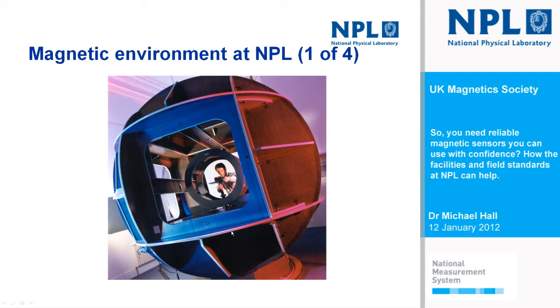The coil that's in the centre is a 1 meter diameter Helmholtz coil, and it's being used to calibrate the 3-axis fluxgate magnetometer along one of the axes, and each of the axes are done individually. There the person is setting that up in the centre of the system, and it's in this region where the larger coil system has cancelled the ambient magnetic field down to less than 1 nanotesla. I'll talk about the noise floor on that, and limitations, and how we are planning to improve and reduce that noise floor in the next few slides.